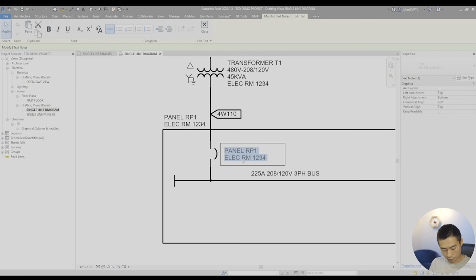So typically a breaker would have three things. It'll say, let's say, 100 amp frame, 100 amp trip, and then three phase. But sometimes you want to put like shunt trip or ST, electronically operated EO, or LSIG for long, short, instantaneous, and ground. So there's a lot of extra things that you want to put into a single line diagram that doesn't fit a prepackaged family.